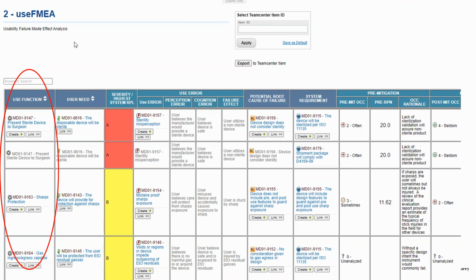And the great thing about the system requirement then is we can progress it down through the V model. So we could say we have a system requirement that's a 11135. Now we can have design requirements that refine that system requirement, and we can have design specifications that get very granular about how we're going to be compliant with that standard, all the way down to, you know, we're going to have a bag seal and it's going to be a 3/8 inch seal, this kind of thing.